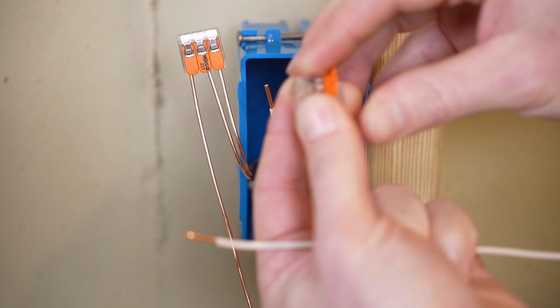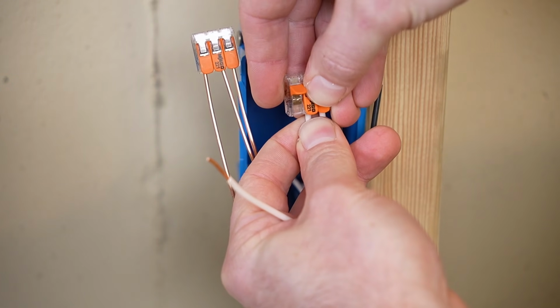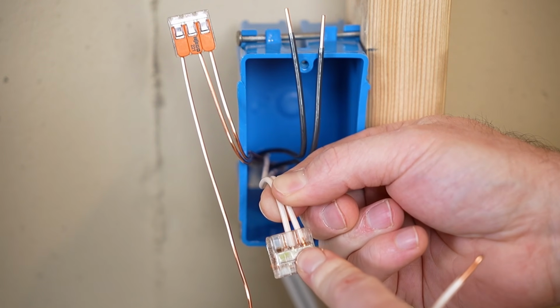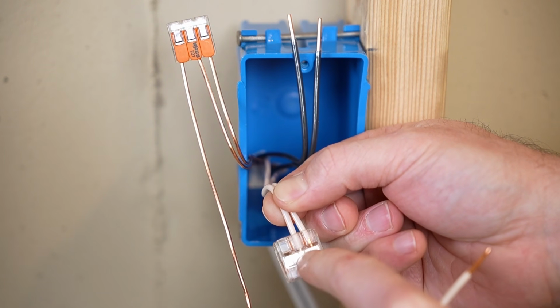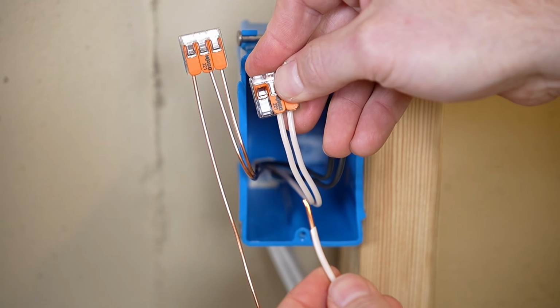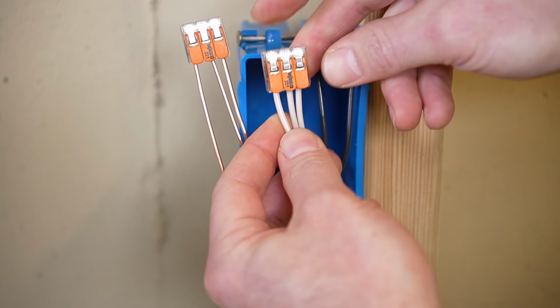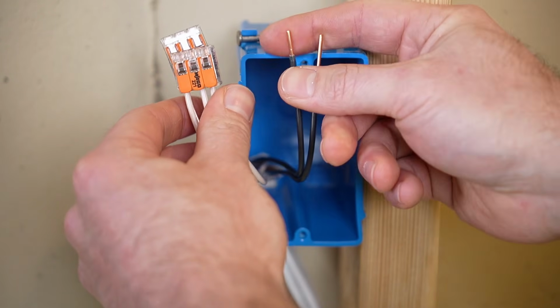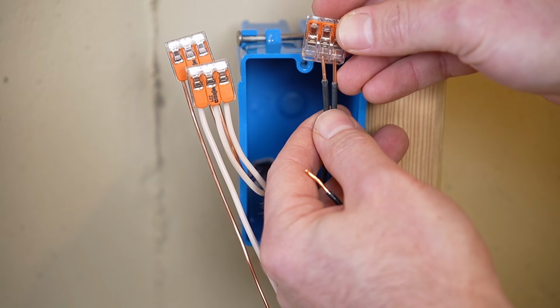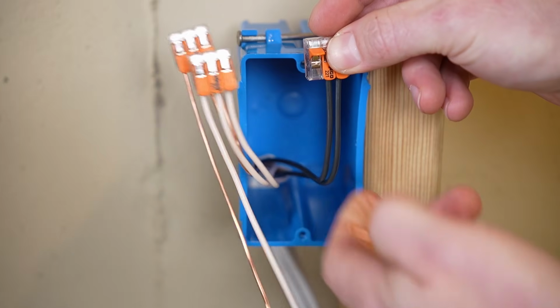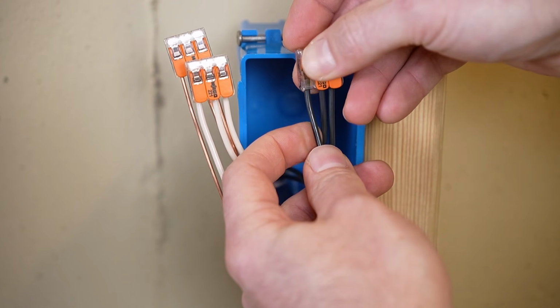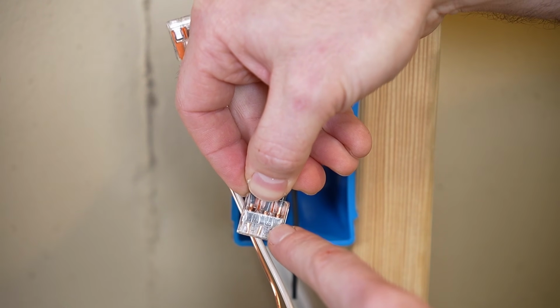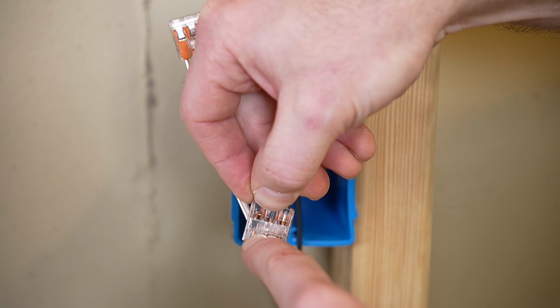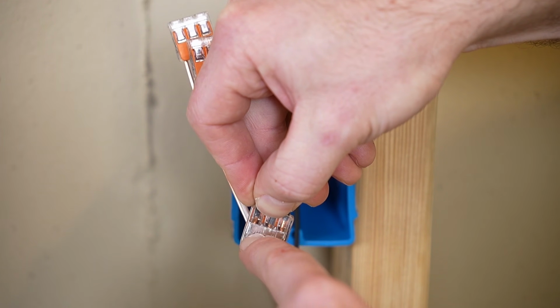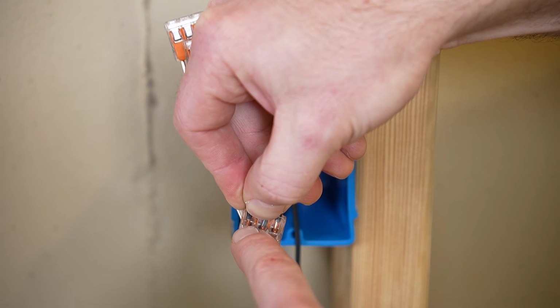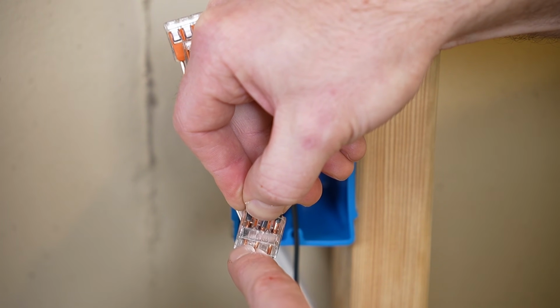Open up the levers, 2 of the neutrals under 2 of the positions. We're going to want to make sure that there is no insulation up underneath that metal strap in the back. And then we install our pigtail in the 3rd and final position. And there we go, our neutral is done. Let's do the same for the hot. So 2 of the hots under 2 of the positions. Close the levers, and our pigtail goes into the 3rd position, and there we go. Same thing, we're going to want to double check that there is no insulation up underneath this metal strip within the Wago connector. Here we can see there is copper visible on both sides of that metal strip, so that's a good connection.